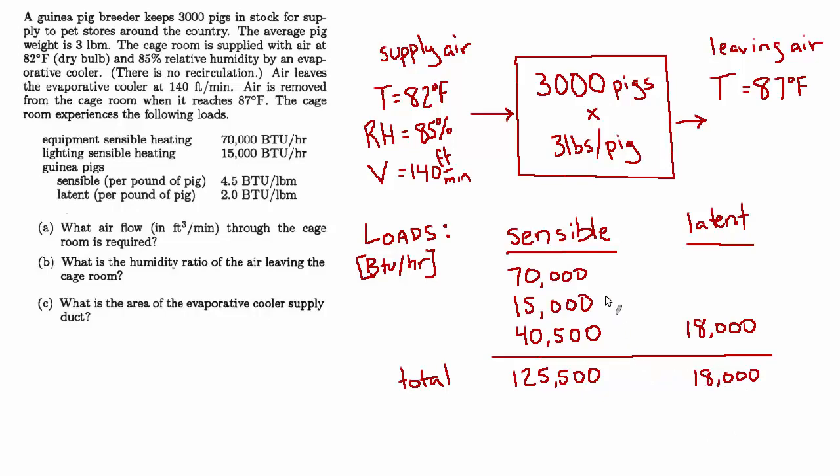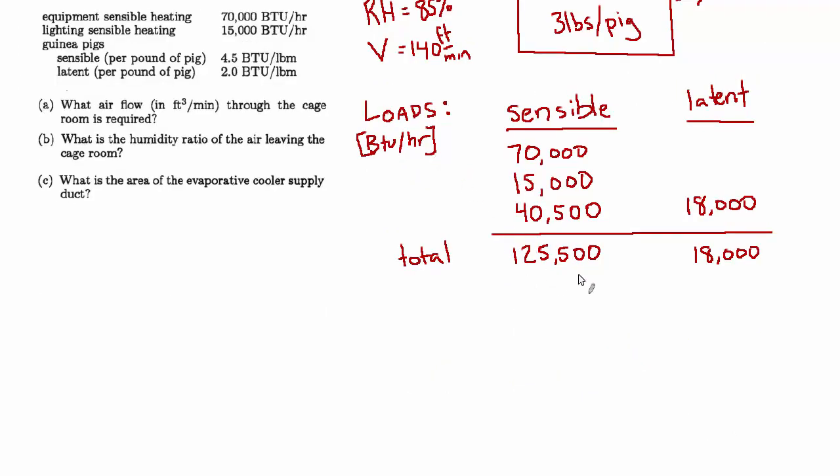So the supply air volume is based only on the sensible load. Because the air is not being returned, we have no desire to control the humidity. We're just going to allow that latent load to be added to the air, and then the air leaves, and the humidity leaves with it, and new air is supplied at these predefined conditions from some evaporative cooler. So for the supply air volume, we'll use our handy rule of thumb.